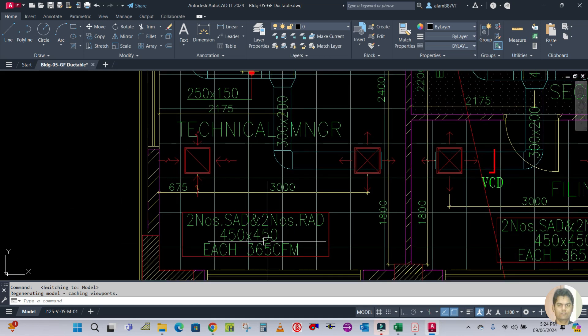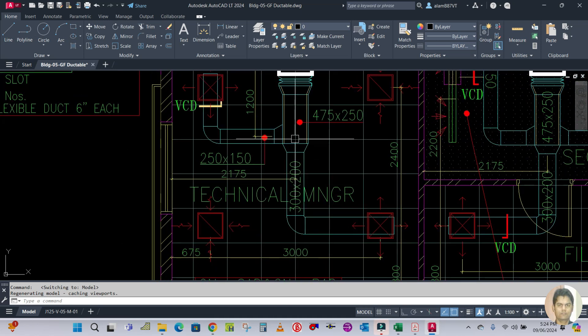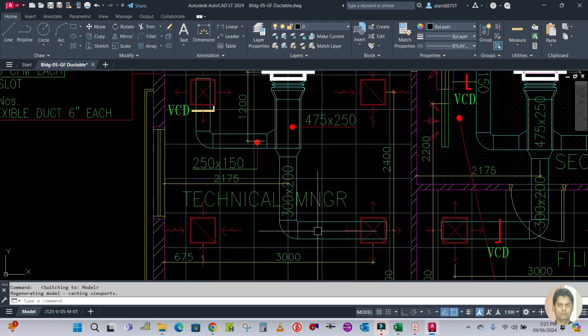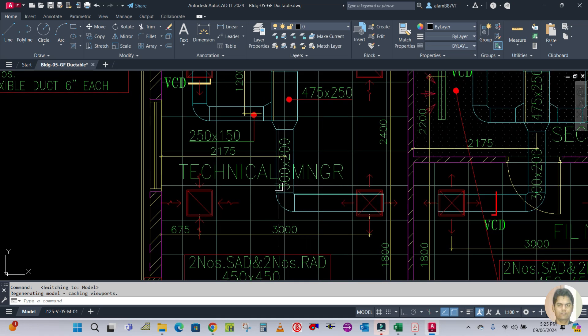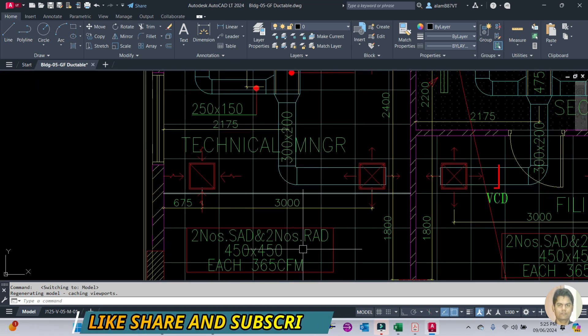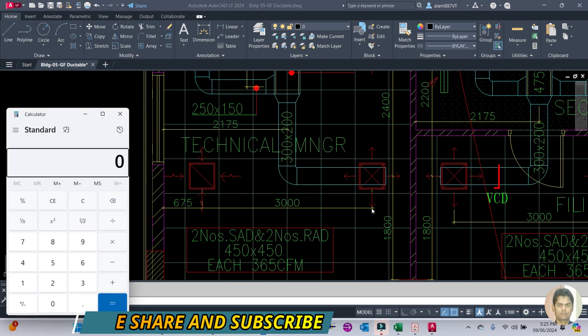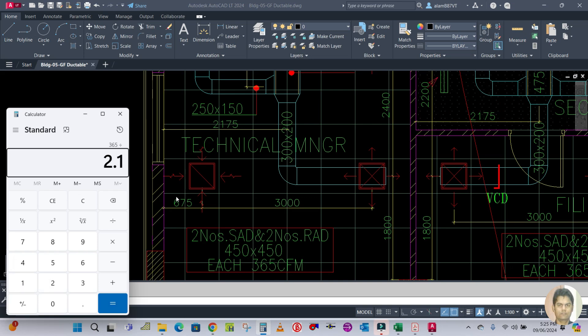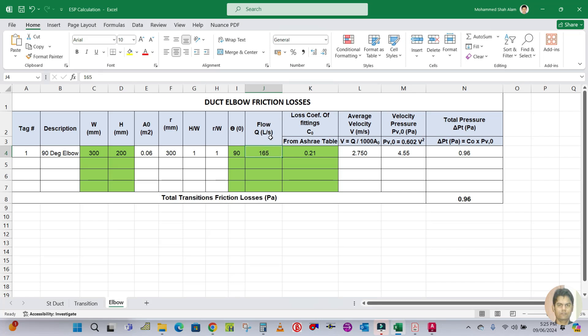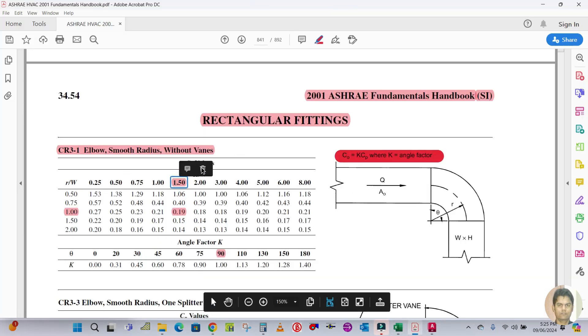From this branch, 365 CFM is flowing through to the diffuser, so the airflow for this elbow is 365 CFM. Convert to liters per second: 365 divided by 2.119 equals 172 liters per second. Enter 172 L/s into the flow field. Now let's calculate the loss coefficient.